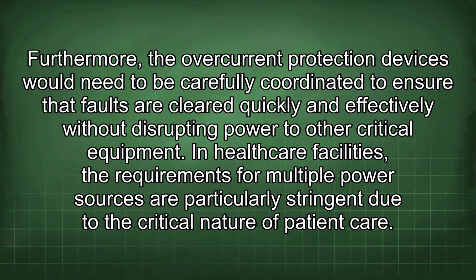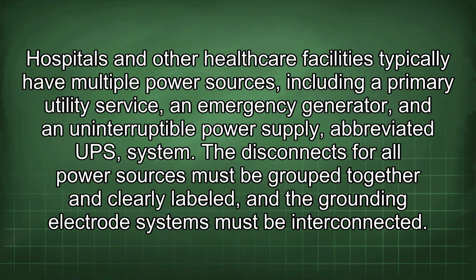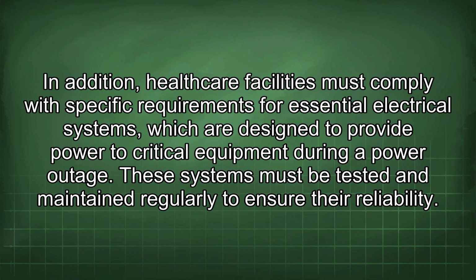In healthcare facilities, the requirements for multiple power sources are particularly stringent due to the critical nature of patient care. Hospitals and other healthcare facilities typically have multiple power sources, including a primary utility service, an emergency generator, and an uninterruptible power supply, abbreviated UPS system. The disconnects for all power sources must be grouped together and clearly labeled, and the grounding electrode systems must be interconnected. In addition, healthcare facilities must comply with specific requirements for essential electrical systems, which are designed to provide power to critical equipment during a power outage. These systems must be tested and maintained regularly to ensure their reliability.